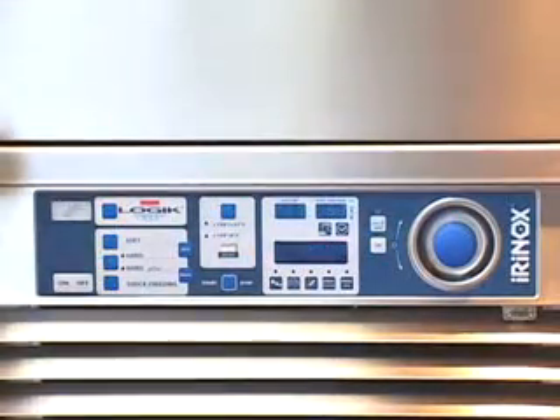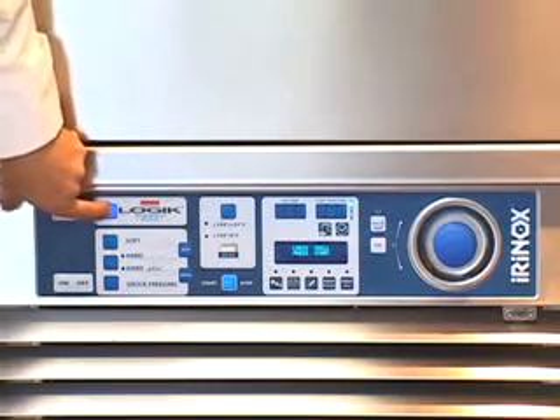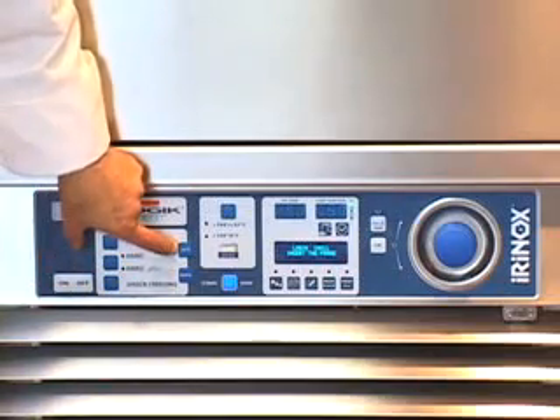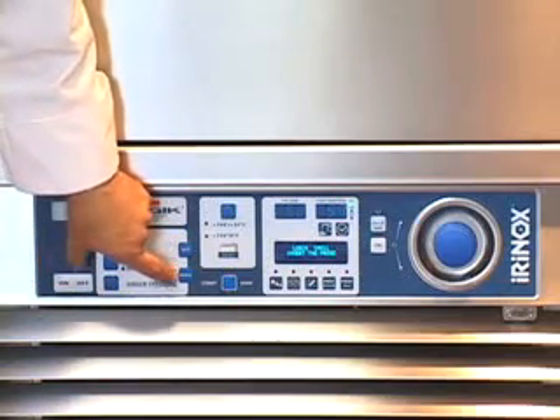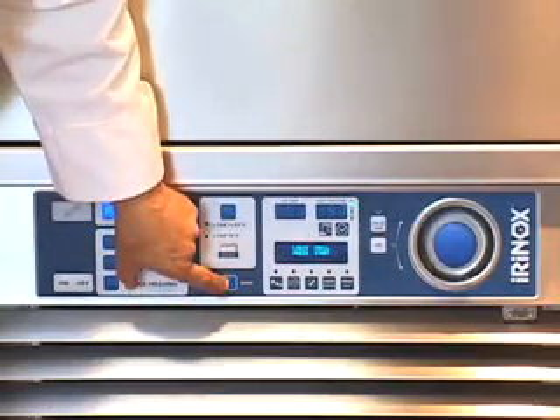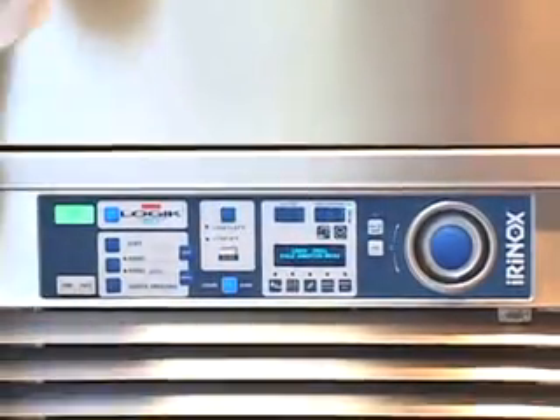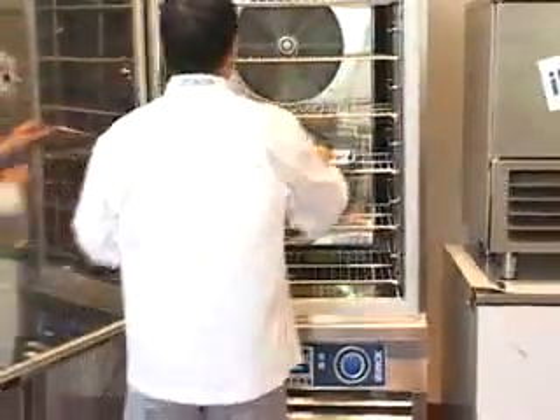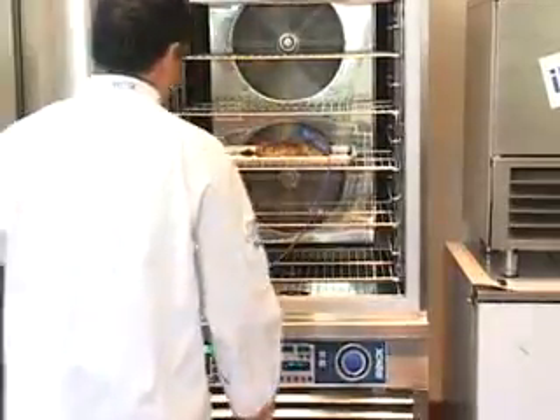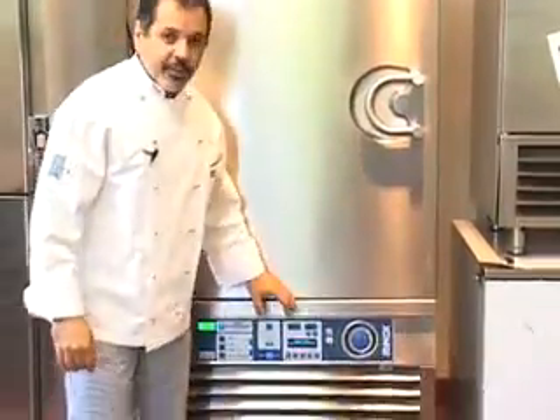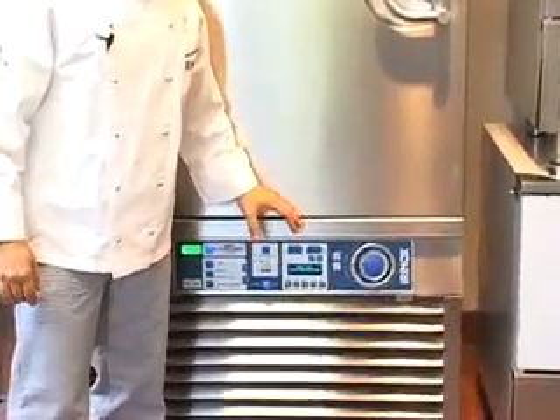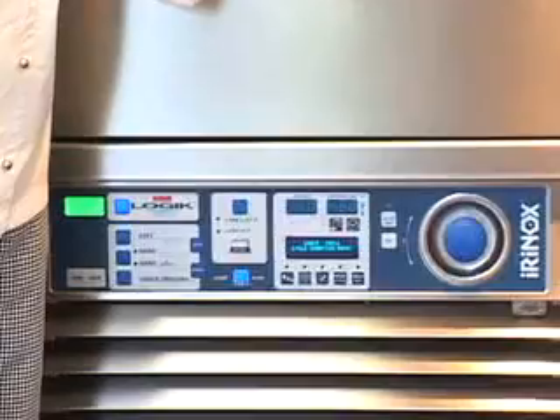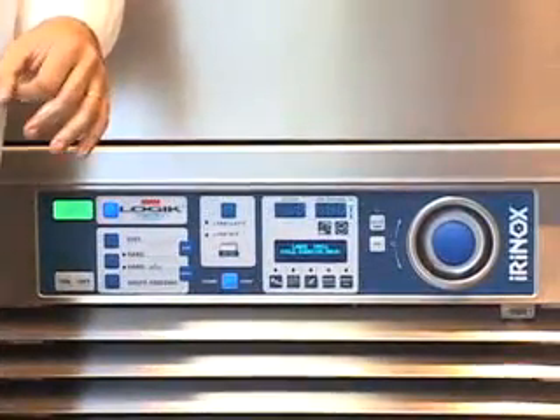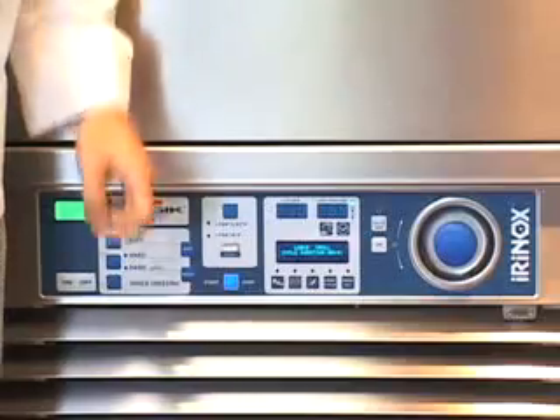I'm now going to demonstrate the Logik chilling mode, which is a chill mode only. When I select the Logik chill cycle, you notice the auto and manual buttons do not light up because it requires the probe only. I hit the start button and I can choose my broccoli, again the chicken, anything I want. I put it in the chiller, I insert the probe, and I close the door. The unit will automatically monitor the core temperature of the product and adjust the air temperature accordingly to bring the product as rapidly as possible down to 37 degrees, and then go into an automatic hold mode until I stop the unit.